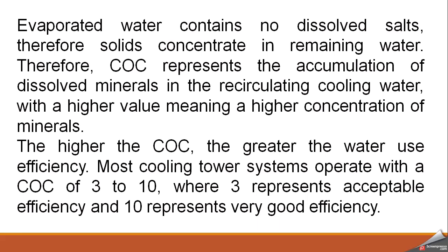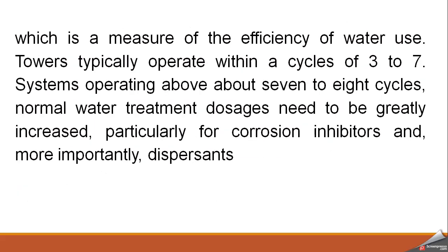So most cooling tower systems operate with a cycle of concentration, that is COC, of 3 to 10, where 3 represents acceptable efficiency and 10 represents very good efficiency. However, with this increasing efficiency, certain problems also arise. We have to compromise between the water usage efficiency and the other parameters which are affected due to the increase in solids in the cooling tower water.